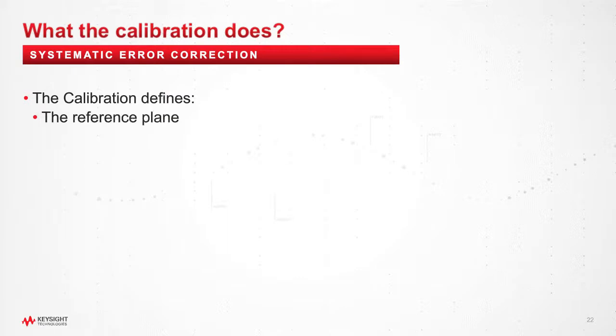So what does the calibration do? Well, the calibration corrects for the reference plane, as we just said, and the reference impedance. Because remember, the output of a mixer is just a memory location. You want in reality to measure some reflection coefficients referred to a certain reference impedance.